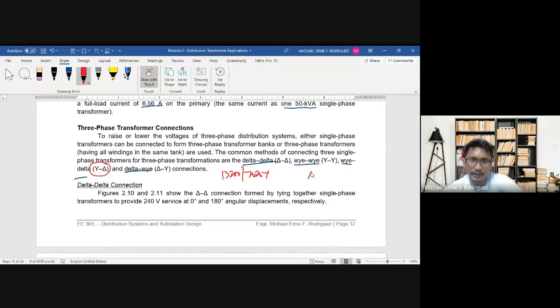Some also use delta to Y, because their output on the secondary side becomes Y, which is 400 by 230. The 400Y connection, being a Y connection, has 230 volts. Some companies or establishments have motors that run on 400 volts, so that's 400 volts line to line and 230 volts line to neutral.